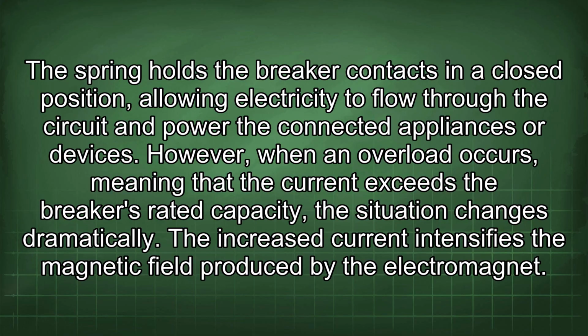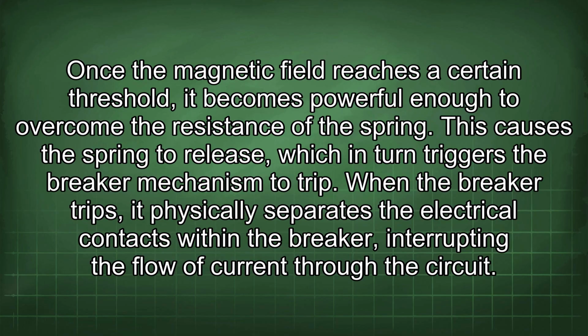The increased current intensifies the magnetic field produced by the electromagnet. Once the magnetic field reaches a certain threshold, it becomes powerful enough to overcome the resistance of the spring. This causes the spring to release, which in turn triggers the breaker mechanism to trip.